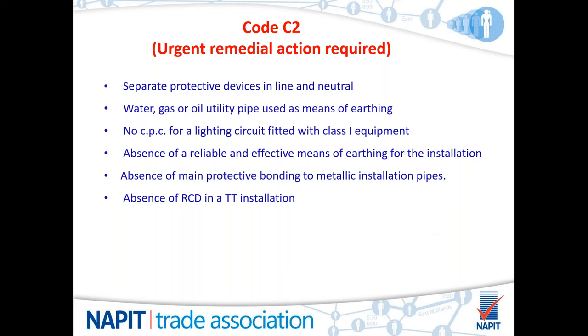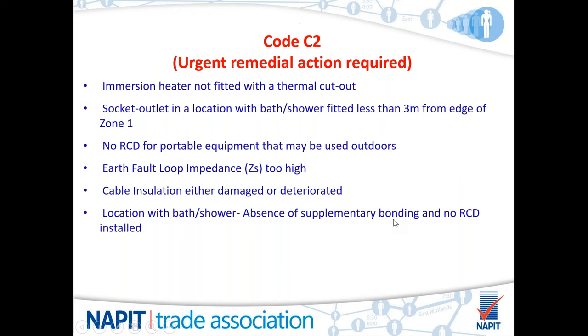And of course, a TT installation with the high earth fault paths, resistive earth fault paths, and no RCD to take out the protective devices, then again, you are putting people in possible danger. Other potential code twos you may come across could be an immersion heater not fitted with a thermal cutout, a socket outlet in a location containing a bath or shower fitted less than 3 metres from zone one. So there's the potential for using a hairdryer while in the bath or anything daft like that.